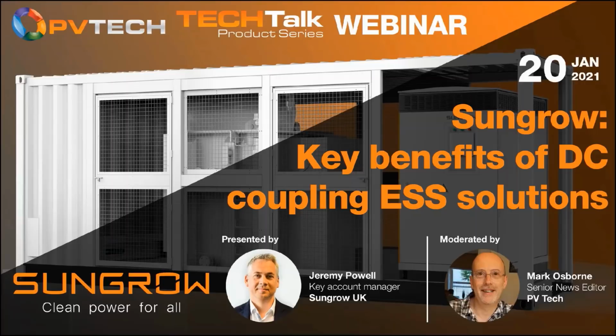With the batteries themselves, it can work with different C ratings: the 1C, which is 1 hour, 0.5C, which is your 2-hour battery, and we can go down to 0.25C as well with that system. So when we're talking about yield capture or curtailment, grid curtailment, we're able to store a lot more of the yield into the batteries, because it's a longer duration import and export of the batteries.